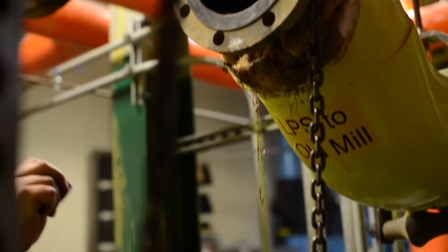And that's generally where we do, if we have any big repairs to do, shutdown is the time we do the big repairs. The shutdown allows us to add new equipment. A couple of years ago, we put in a large air and dirt separator on the chilled water system, which allows us to have a more efficient operation of the chilled water system. That could only be done if the system is down, because you have to cut into the piping. So we take advantage of the shutdown to do some of these major modifications for energy efficiency and improvement of the operations.